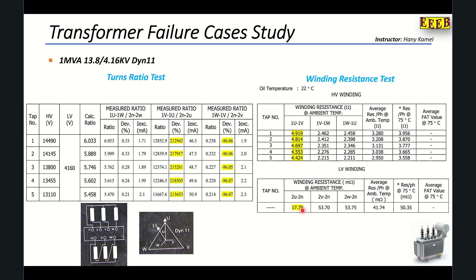On the LV side, we can see the V phase and W phase readings, but the R phase (U phase) is very small compared to the other two phases, meaning there is a short circuit on this winding. Because of this short circuit on the LV winding and the cut on the HV winding, there is a ratio error and more excitation current present during the turns ratio test.